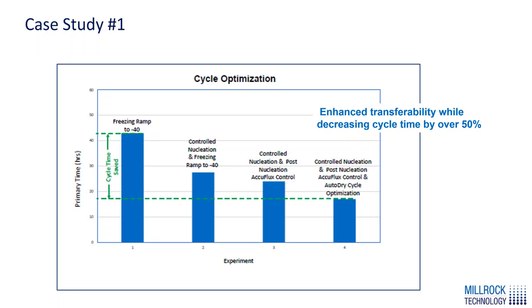Here's an example of a case study using sucrose. We used a standard cycle where we froze the product to minus 40 at half a degree C per minute and then went into primary drying, holding shelf temperature and pressure constant, resulting in a pretty long primary drying time. We then stepped through the available options in freezing — from controlled nucleation, to controlled nucleation with heat flow control after nucleation, and using auto-dry to control the product temperature close to but less than the critical temperature. We reduced the primary drying time by over 50%.